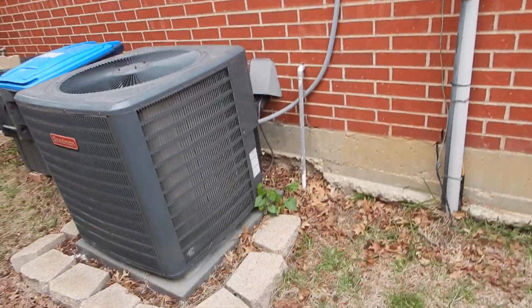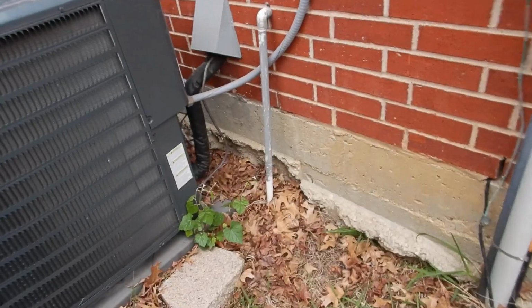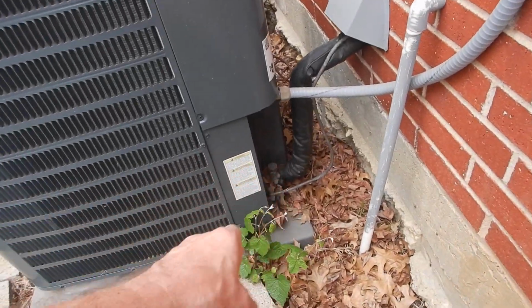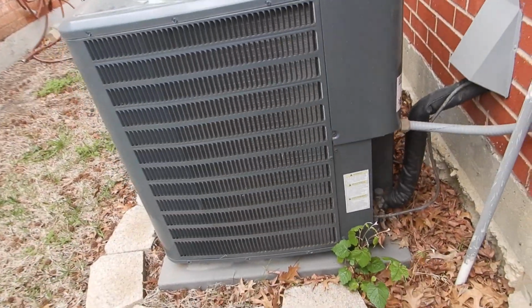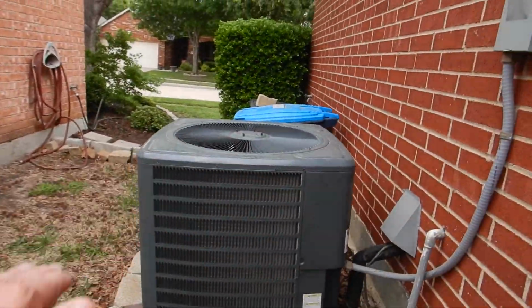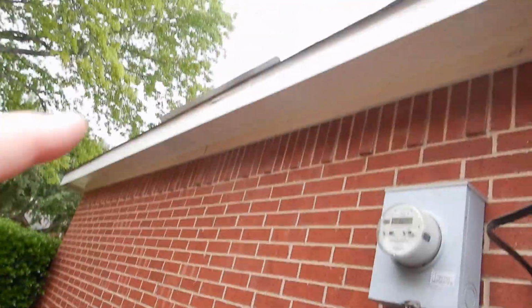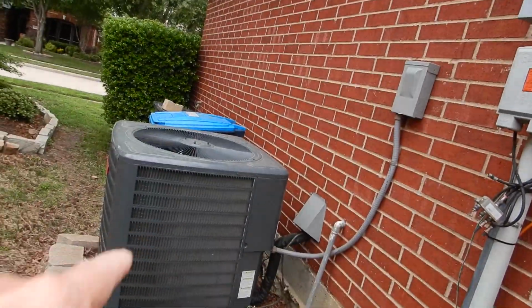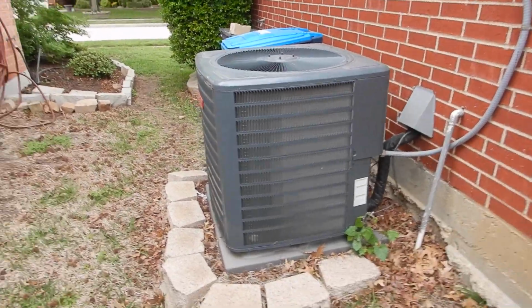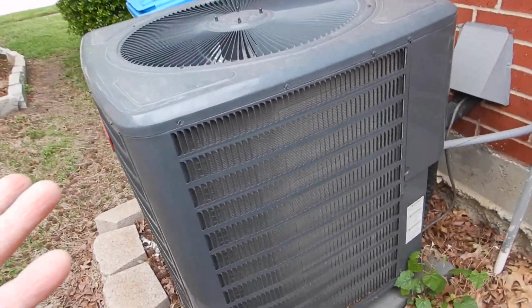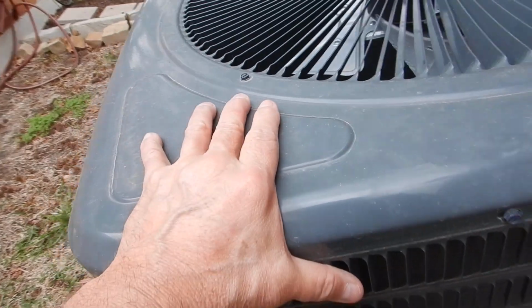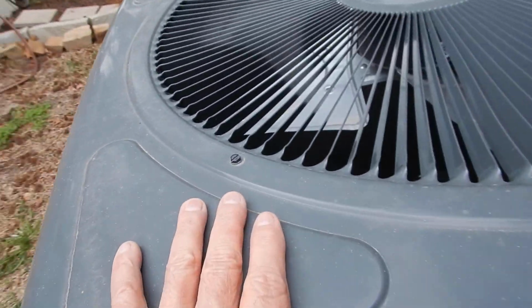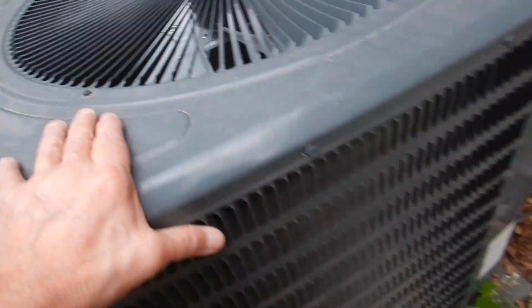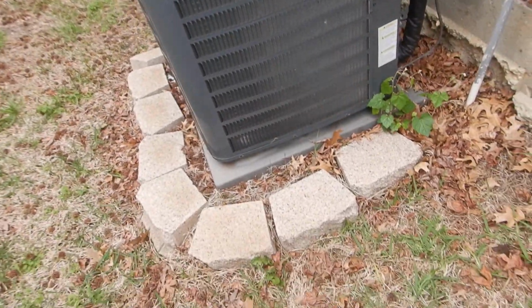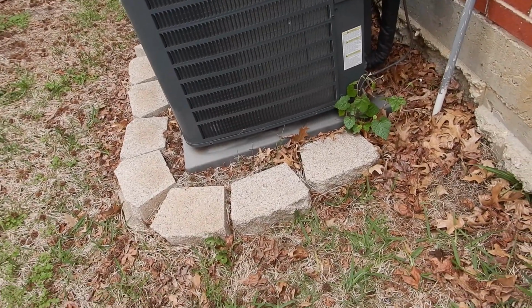Our disconnect should have been sealed. We've got the wrong type of Schrader valve caps. We've got dirty coils, and the unit is not level. And it could have been much better protected against water falling on top of it. The reason why we don't want water falling on top of it is because we want this thing to last at least the 14 years that Las Vegas is betting. We want it to last 35 years. We want it to last forever. But we got to take care of it.